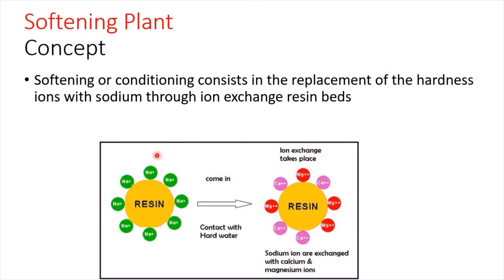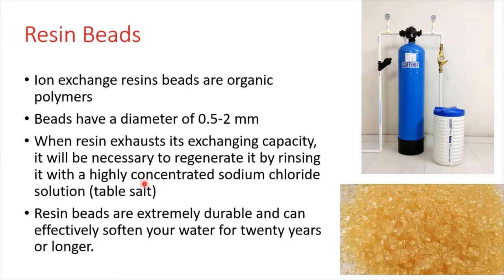We rinse the resin beads with the table salt solution to regenerate the sodium ions. On the extremities of each bead, sodium ions are attached, and to regenerate them we rinse the beads with NaCl — table salt solution. The resin beads are very durable; there is no need to change this media. It can last at least 20 years or even longer if the softener is effectively maintained.